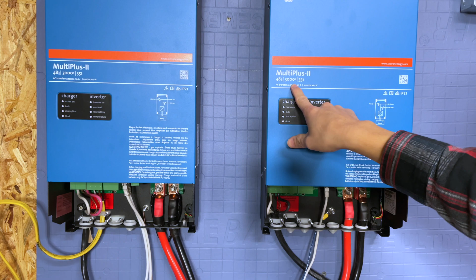The point is, make sure you get 2 units that are exactly the same. This unit is only 3000 VA, but they make this MultiPlus-II series in multiple voltage ranges - 12 volt, 24 volt, and 48 volt models, and maybe others. On each voltage there are different capacity units, like 2000 VA, 3000, 5000, 8000, 10,000, 15,000. It all varies, and depending on which model you get, the transfer and charge capabilities change accordingly. Just keep that in mind. In this example we're using 3000 VA units, but when you're setting up split phase, make sure you get 2 that are exactly the same.